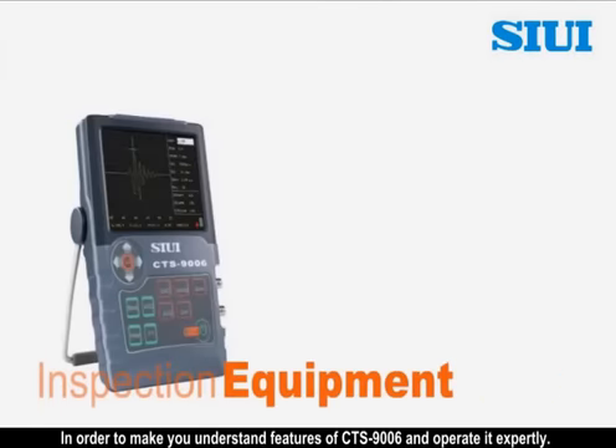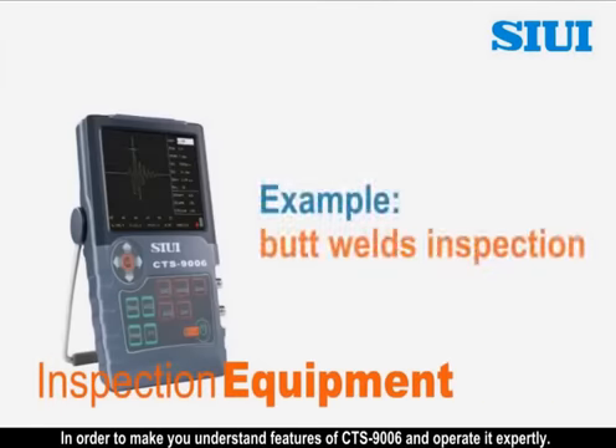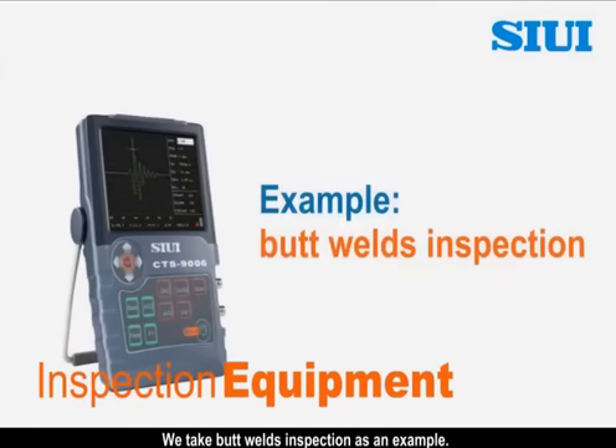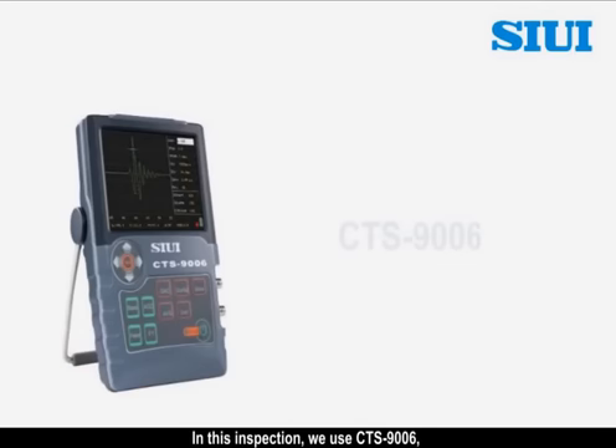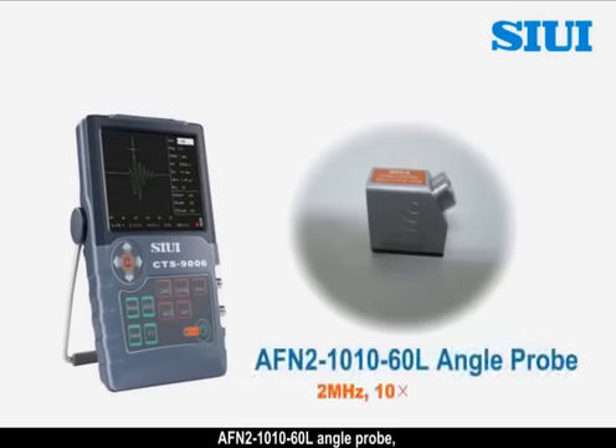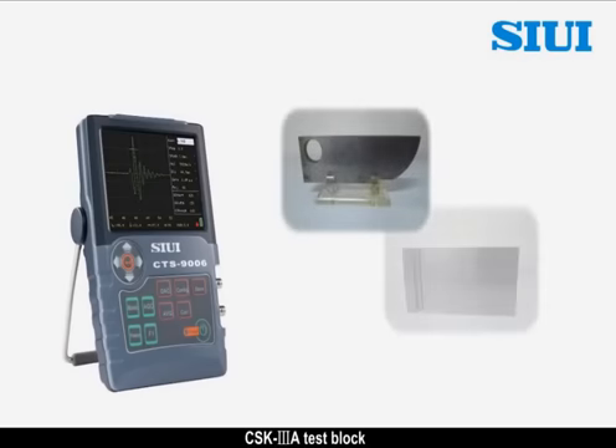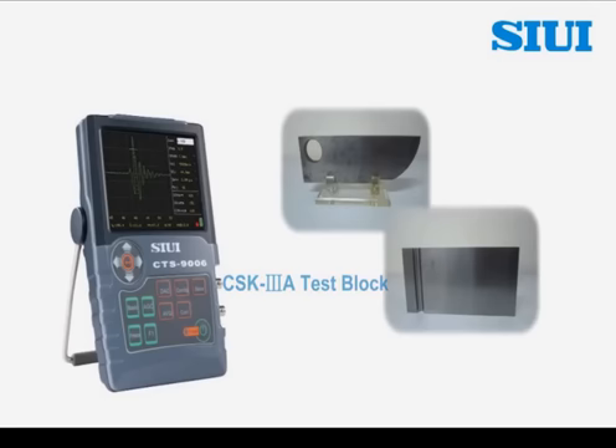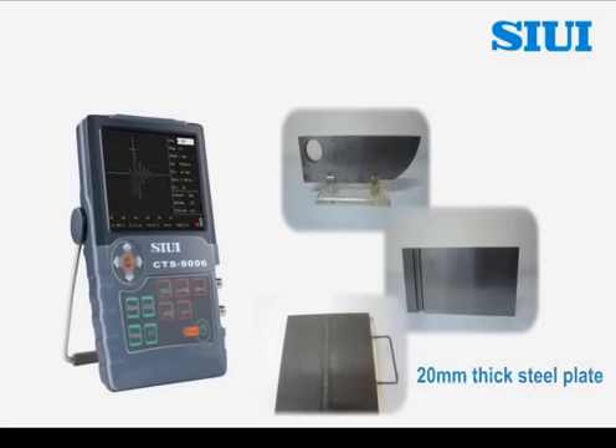In order to make you understand features of CTS-9006 and operate it expertly, we take butt welds inspection as an example. In this inspection, we use CTS-9006, AFN2 1010-60L angle probe, V1 test block, CSK3A test block, and 20 mm thick steel plate.